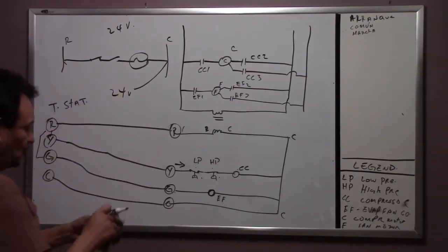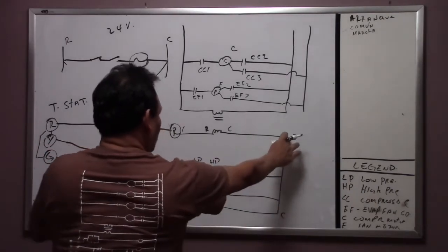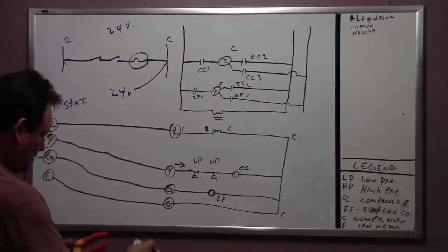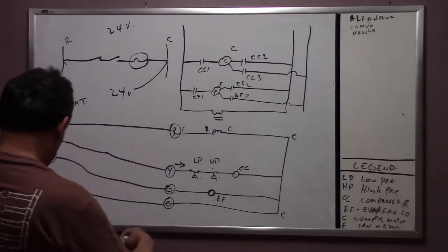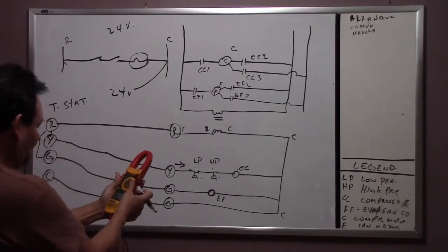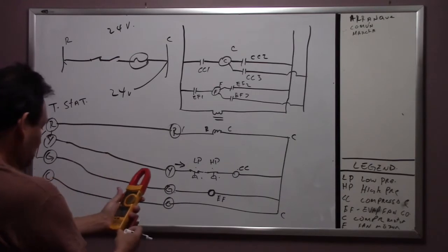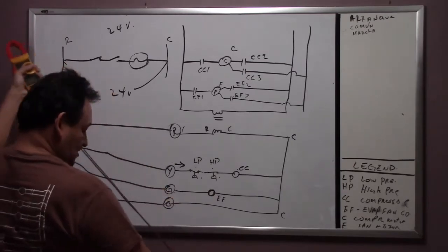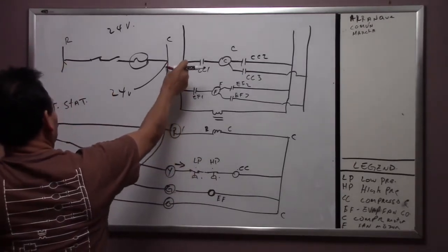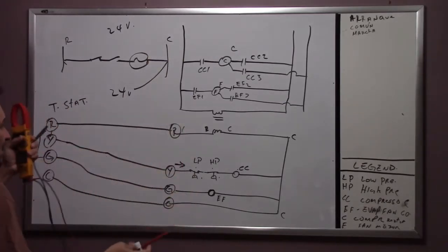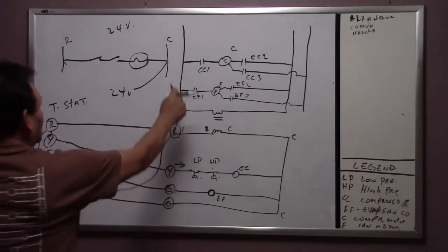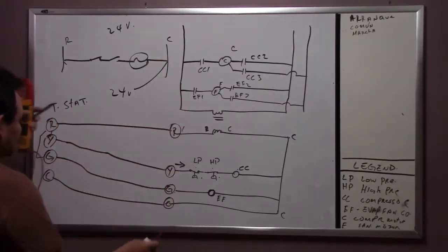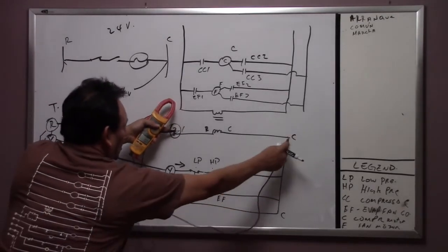on the coil itself, common, we're going to put our lead on the meter, something here, check. It's a Fluke meter, by the way, it's kind of old, a 336 meter. Anyway, we're going to put one lead on common, and then the other one, we're still going to check if we got 24 volts, because we don't know what it is. So we're going to check common and R, right? We're going to get 24 volts, which will be the same thing as checking common and R, okay?